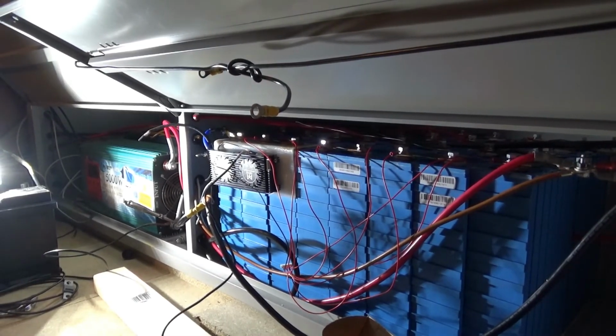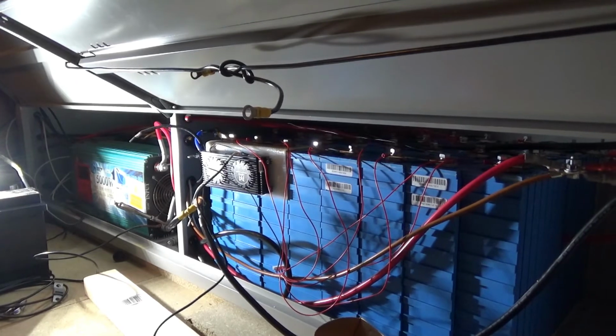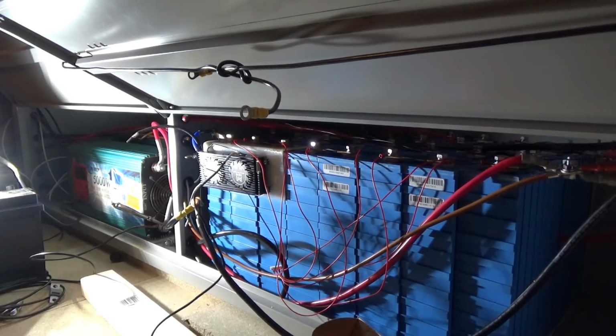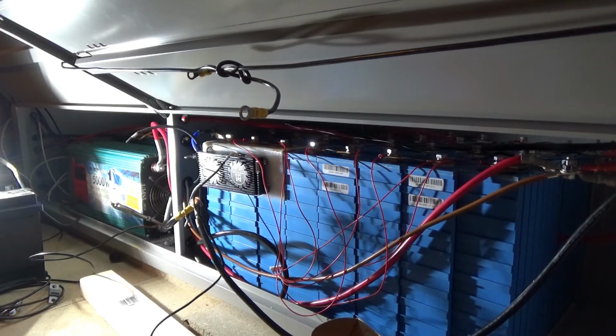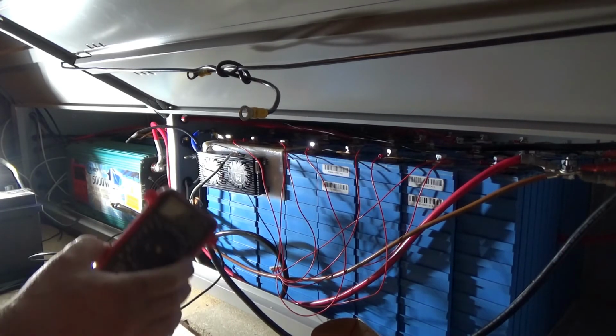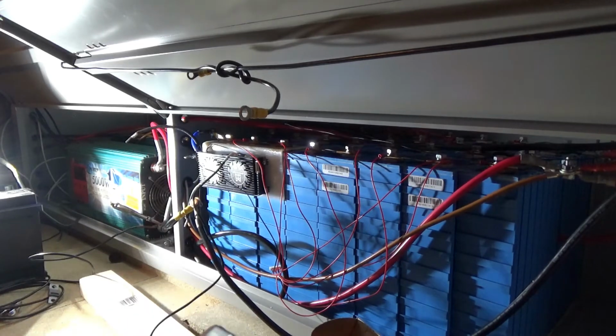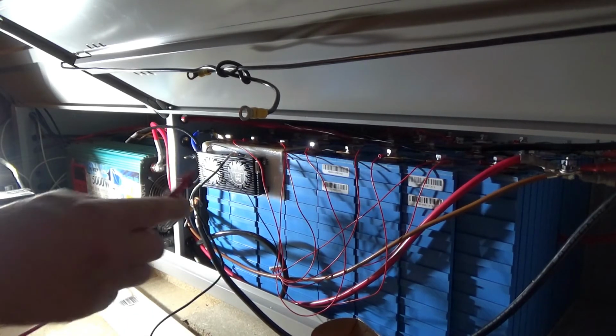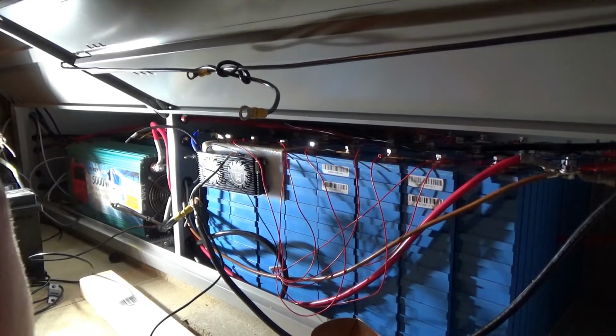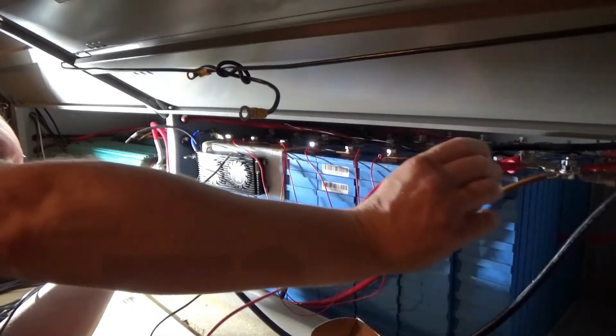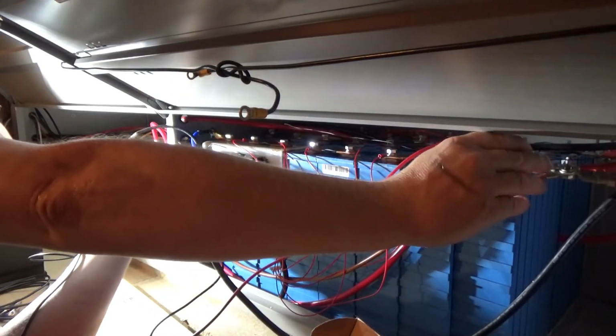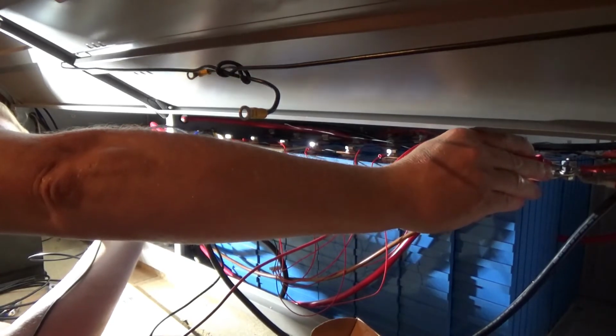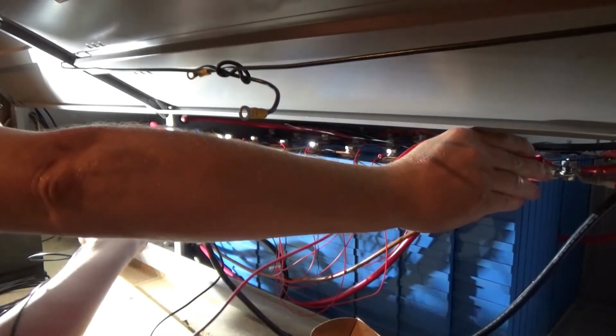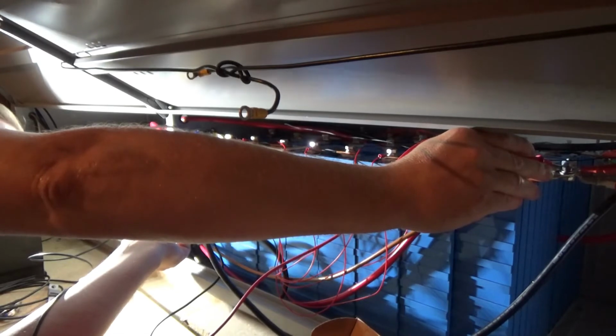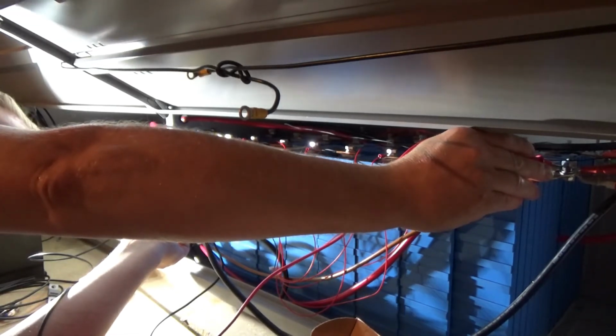Alright, the BMS is in place. It's on a 100 amp fuse connected to the battery minus on the minus side. I have my voltmeter set up in 200 volts DC. I'm going to put the red lead onto the positive side now, and we'll test battery voltage, which is 26.5, and the output side, which is 17.